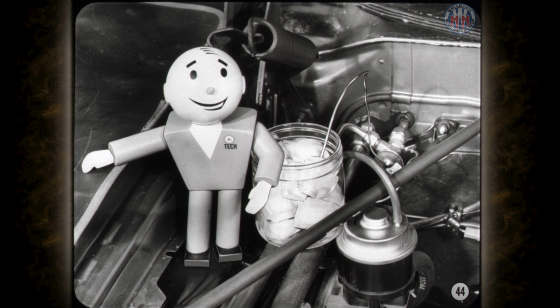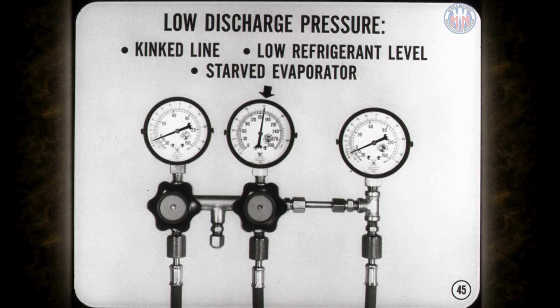Okay, how do you tell which condition is causing the flooding? Cool the expansion valve thermal bulb in ice water. If the pressure's dropped, the valve's working okay. So too much refrigerant is the answer. Right, Fred? Right, Tech. Now, at the other extreme, when you get discharge pressure that's lower than normal, it's usually a sign that the evaporator's not getting enough refrigerant.